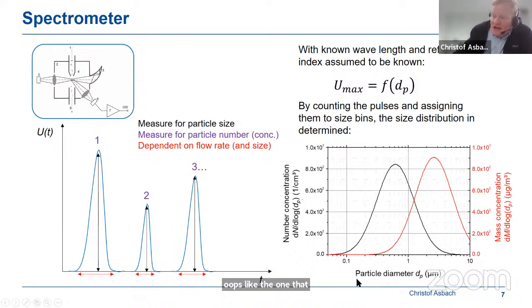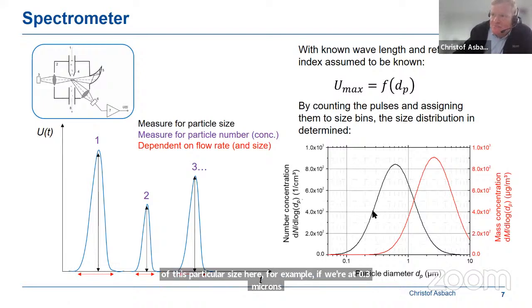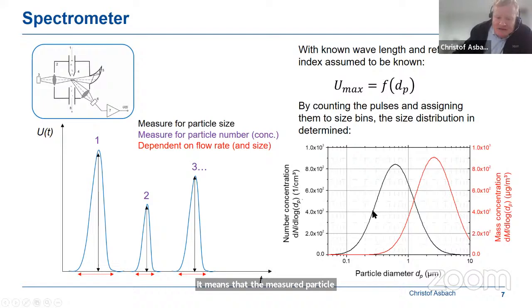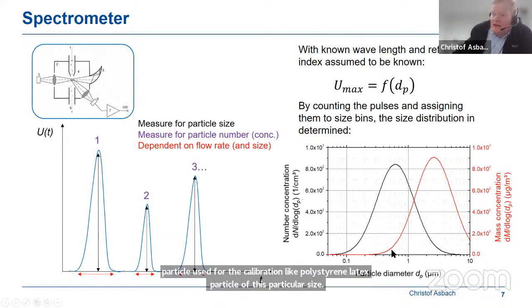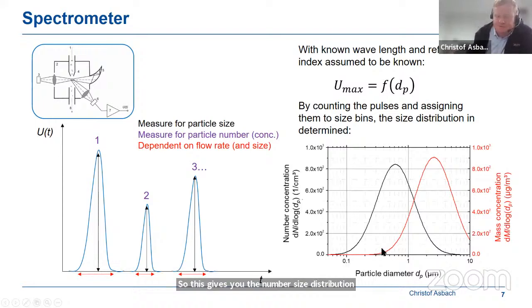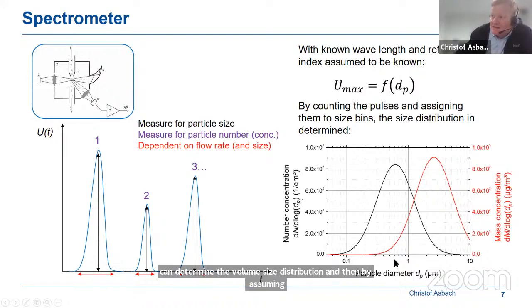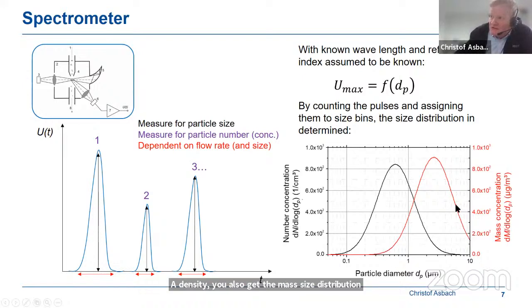And the particle diameter now is something that's called an optical equivalent particle diameter. That means that for particles of this particular size, for example, if we're at 0.3 microns, it means that the measured particle scatters the same intensity of light as a particle used for the calibration, like a polystyrene latex particle of this particular size. So this gives you the number size distribution. And then by assuming that these particles are spherical, you can determine the volume size distribution. And then by assuming a density, you also get the mass size distribution. This is what's printed in red here as an example.